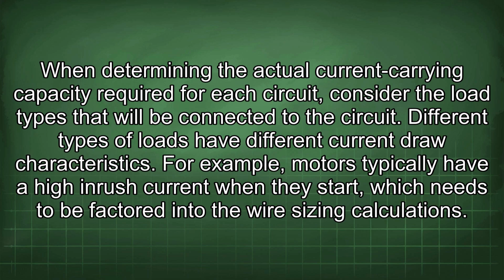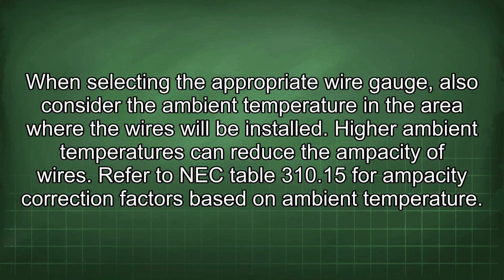When selecting the appropriate wire gauge, also consider the ambient temperature in the area where the wires will be installed. Higher ambient temperatures can reduce the ampacity of wires. Refer to NEC Table 310.15 for ampacity correction factors based on ambient temperature.